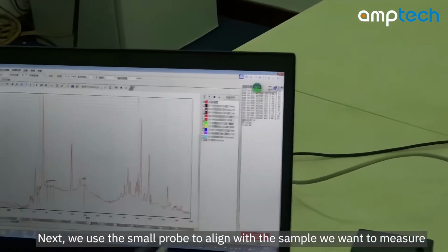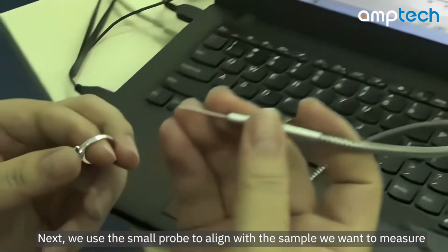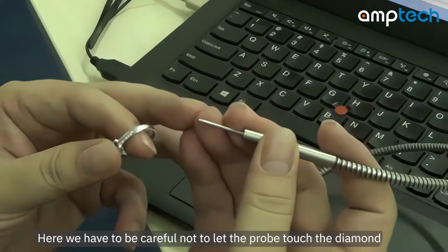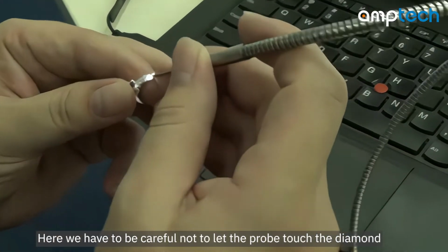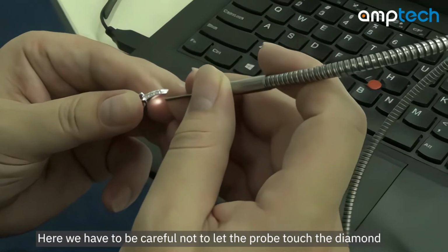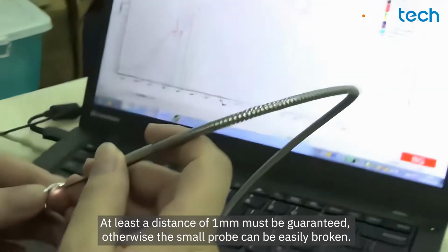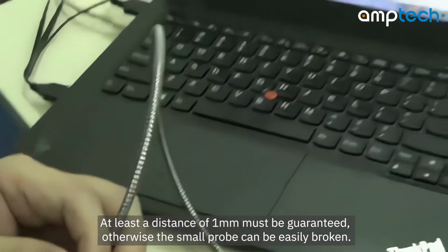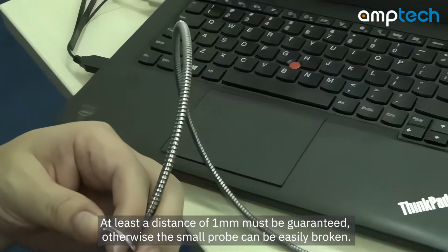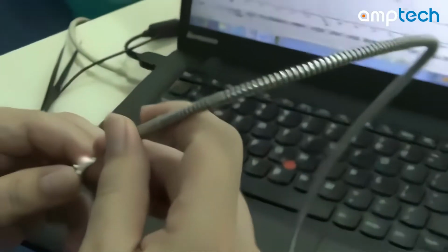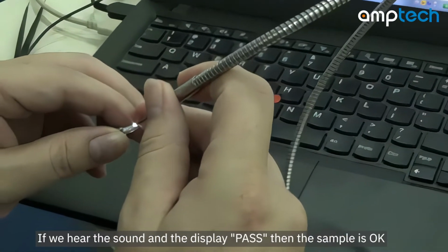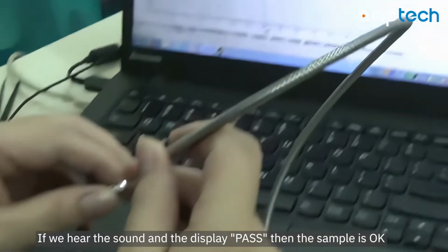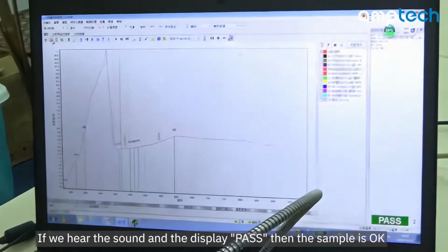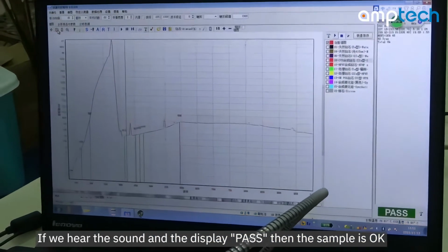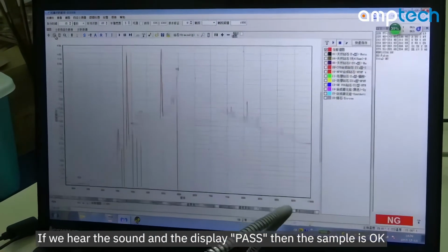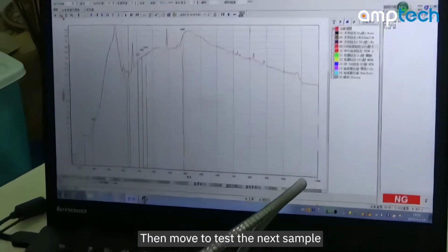Next, we use the small probe to align with the sample we want to measure. Here we have to be careful not to let the probe touch the diamond. At least a distance of 1 mm must be guaranteed, otherwise the small probe can be easily broken. If we hear the sound and the display PASS, then the sample is okay. Then move to test the next sample.